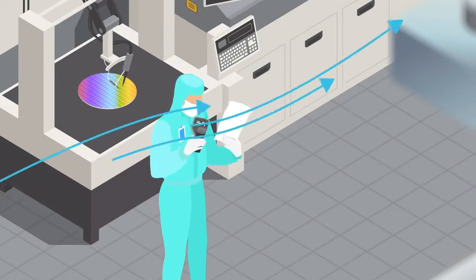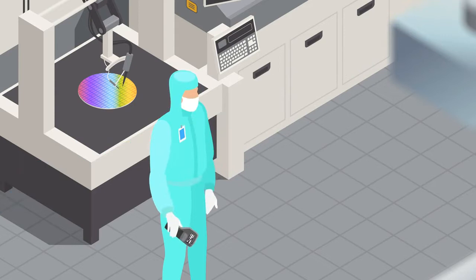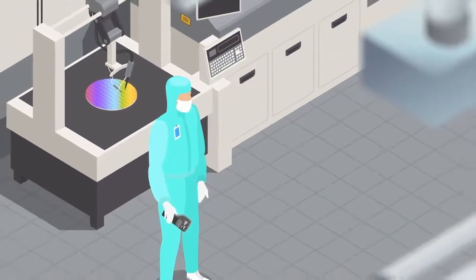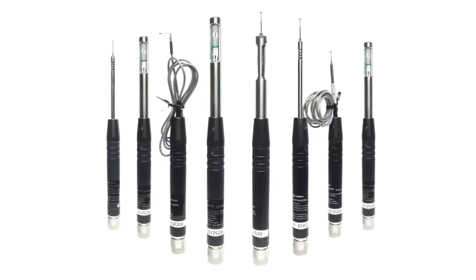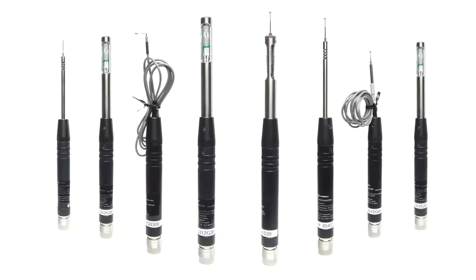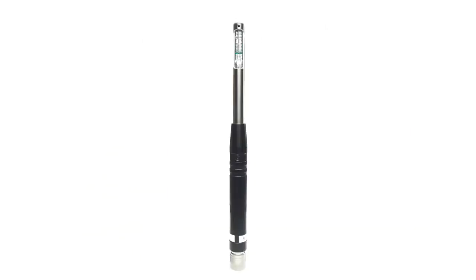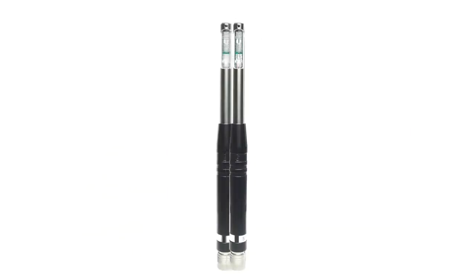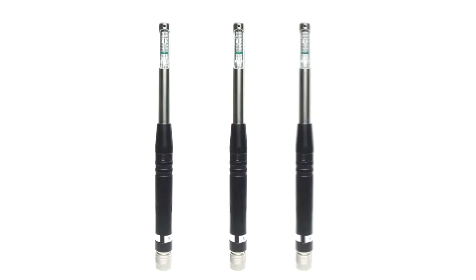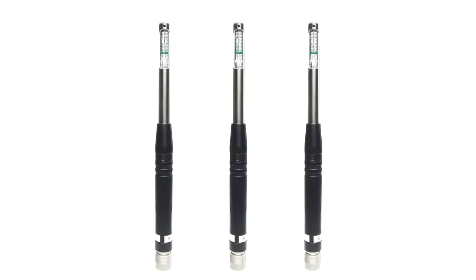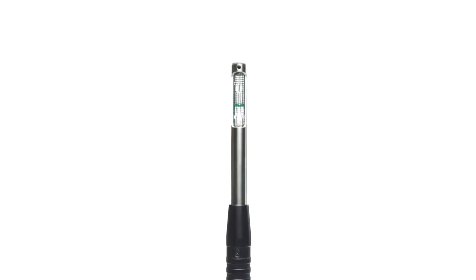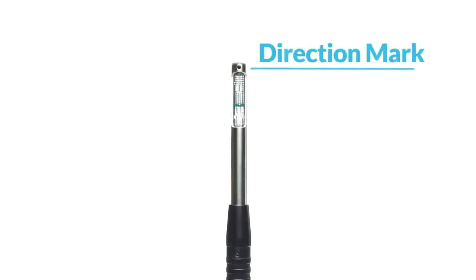Measuring airflow can be a tricky matter, especially when dealing with airflow that varies greatly across different parts of the system or room. This is why having multiple probes, specialized for different conditions, is crucial for making sure you get the best results on any job you take. Unidirectional probes like Model 6531, 6541, and 6561 are ideal for conditions when air is moving in one direction. When using them, be sure to point the sensor in the correct direction by using the direction mark.